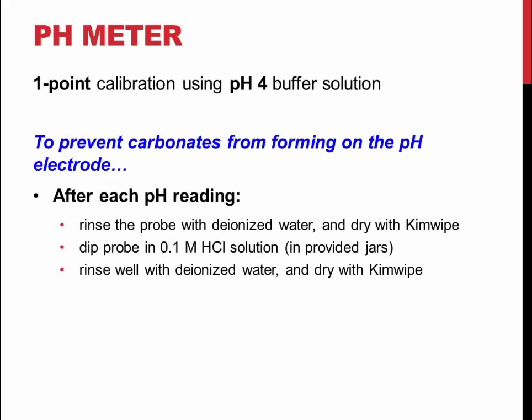To prevent build-up of solids on the probe, it is important to rinse it with water and immerse it in 0.1 M hydrochloric acid solution in between measurements. This will be provided for you in jars in the lab. If you have any questions about proper use of the pH meters, you can also ask your lab instructor.